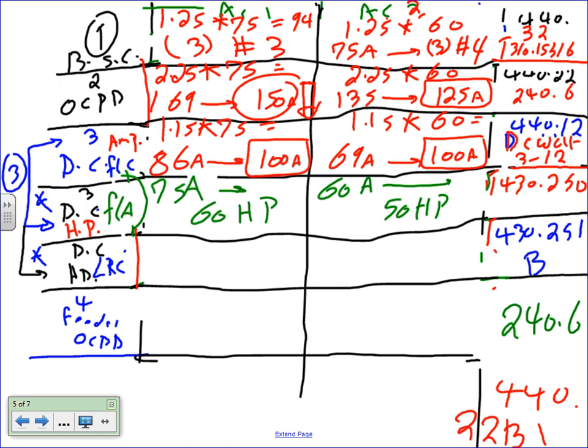Now the second horsepower that you need to size is based on the locked rotor current. The locked rotor current for this one is 400 amp. If you go to table 430.251b, this will translate also to 60 horsepower, believe it or not. And the second one is 360 amp. If you go to 430.251b, this will also translate into 50 horsepower. So can you choose between which is the largest, 50 or 50? It's the same. So you pick the largest of the two. Does that make sense? If that was 50 and that one was 60, you choose, of course, the largest. So for AC number 1, both of them got me 60. For AC number 2, both of them got me 50. So it's 50. But can I get you guys to understand that we have to choose the largest of the two?